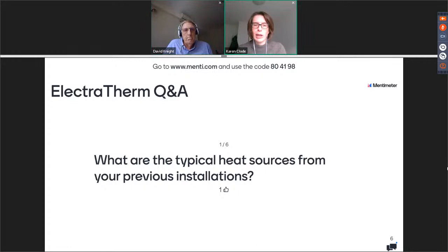Is there any sort of quality that the heat or water needs to be? Is there any requirement on particulates? We need about 500 kilowatts thermal energy available to do the basic operation, and we have high quality water requirements because of the type of heat exchangers on our machine. But that's easily handled by having an intermediate heat exchanger - so we might have a dirty water heat exchanger and our clean water cycle.